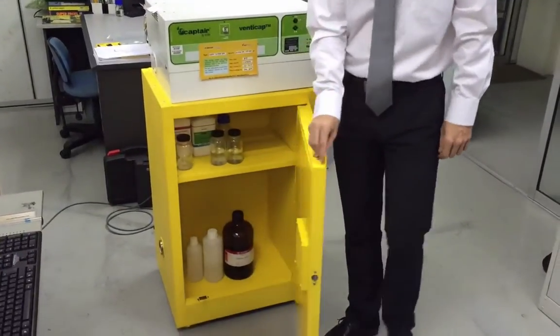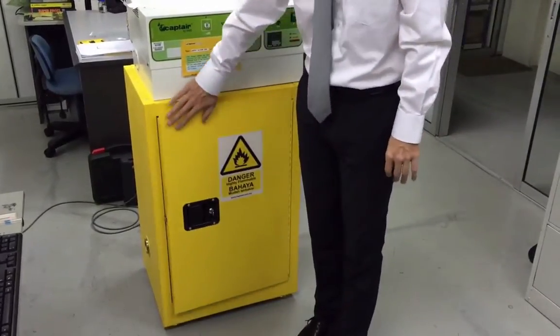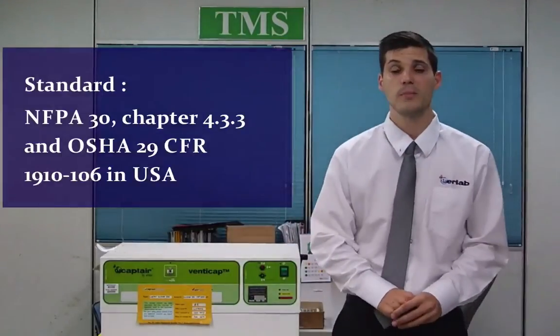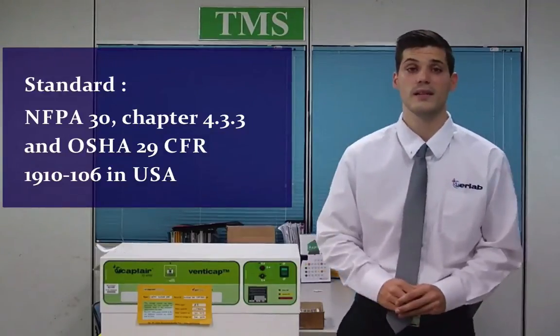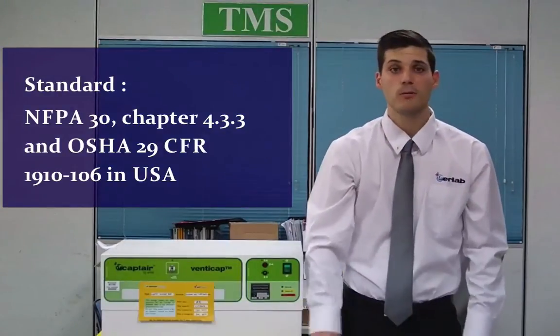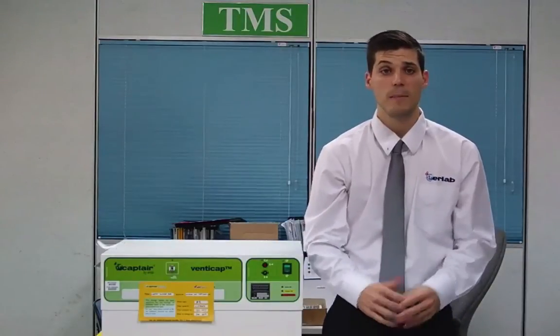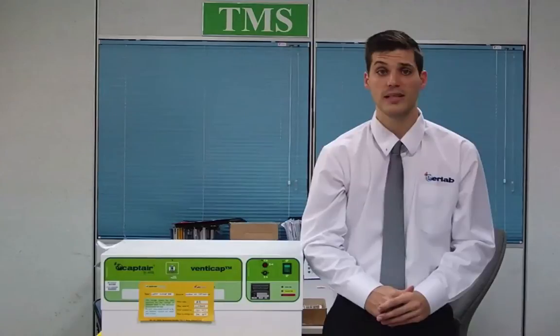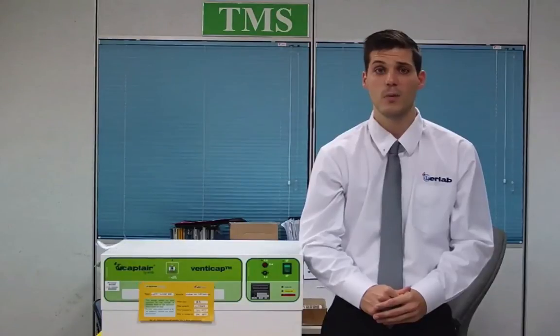The body of fire safety storage cabinets shall be constructed of strong double-wall metal sheet and is designed to resist fire happening outside the cabinet during a period of at least 10 minutes, according to worldwide standards. Many labs are equipped with such cabinets as it's required by insurance companies, but most of those cabinets are not connected to outside ventilation, since it's not easy due to the absence of main ventilation where they are located.